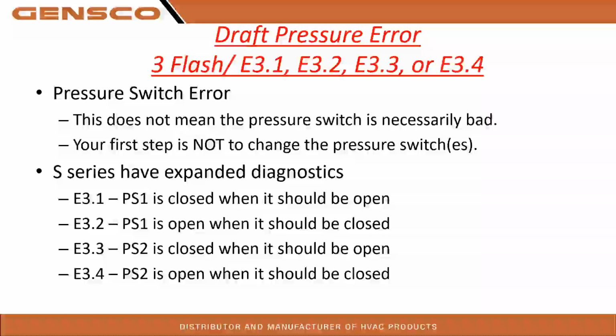So 3.1 is telling you pressure switch 1 is closed when it should be open. 3.2 is open when it should be closed. If you guys are getting pressure switch errors on the S series furnaces, I would start to think you may have a tubing issue or something's not connected right. So I would direct my installers to start looking at the tubing. Make sure everything is where it should be.